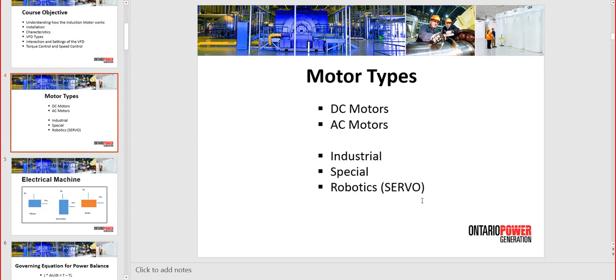So basically for the same price you can have a servo system, and the servo system has many advantages over an induction motor. For instance, the servo system can start and stop all day long and will not overheat. A servo system will have software that makes it easy to control positioning and to write code for different movements, as opposed to an induction motor where you need to do everything by setting up the VFD and eventually add a PLC, a programmable logic controller, that will take care of the different commands to the VFD. So that's the classic way, the way it was done all along. So we will go over this as well.